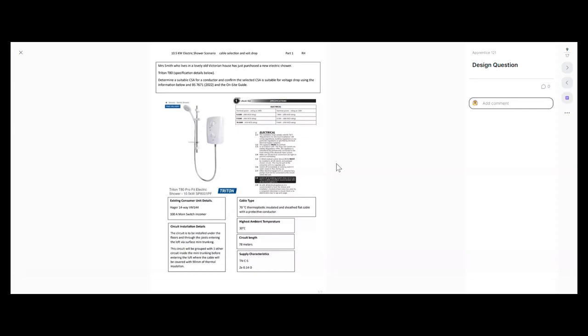So Mrs. Smith lives in a lovely old Victorian house. Anybody that's worked in a Victorian house will know that they've got very tall ceilings and they're generally quite long from front to back, which might explain the length of our circuit a bit later on. She's been to Screwfix and bought herself a brand new Triton T8 electric shower. I've included a bit of information from the manufacturer's instructions — it tells us that it's a 10.5 kilowatt single phase, and some other information regarding electrical items to consider.